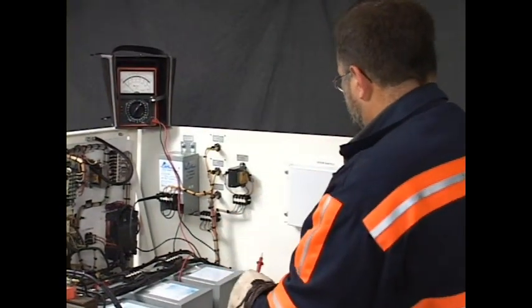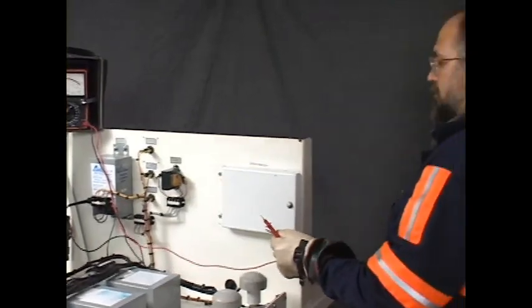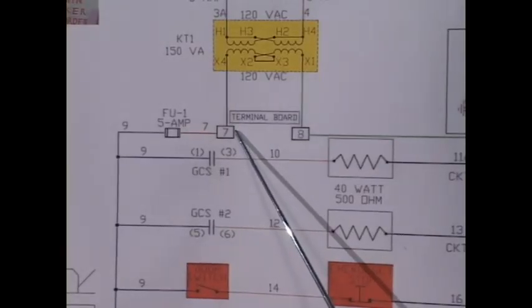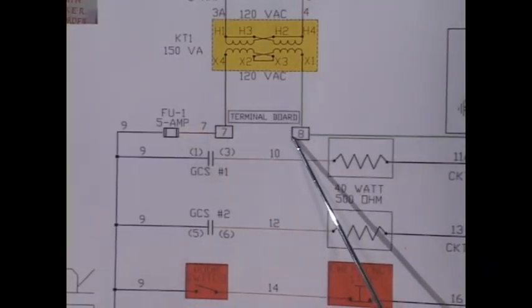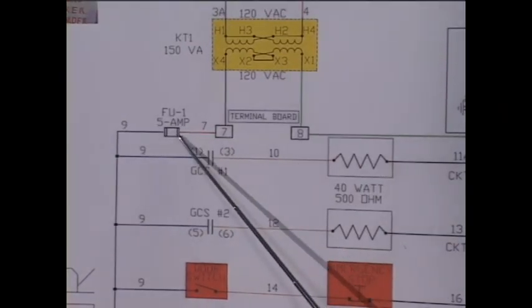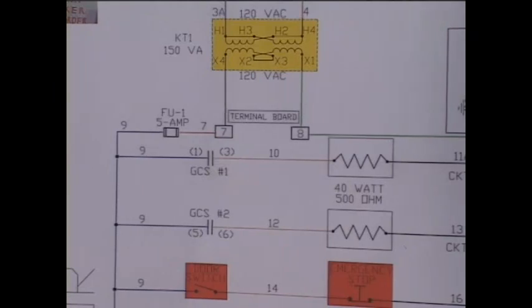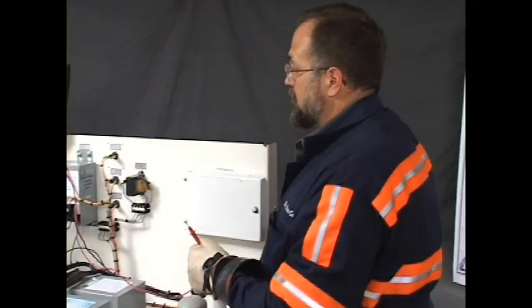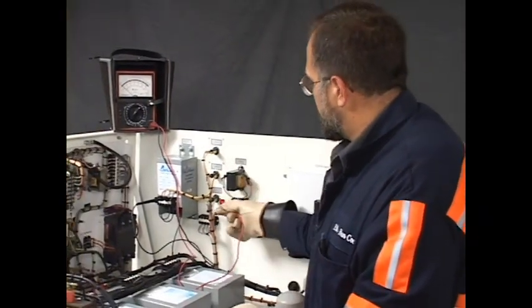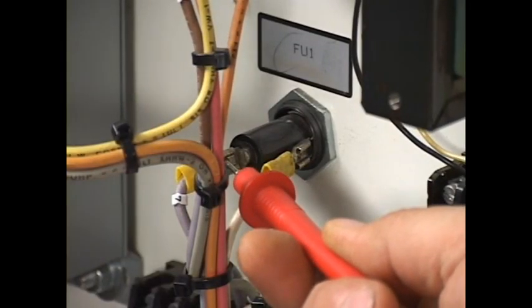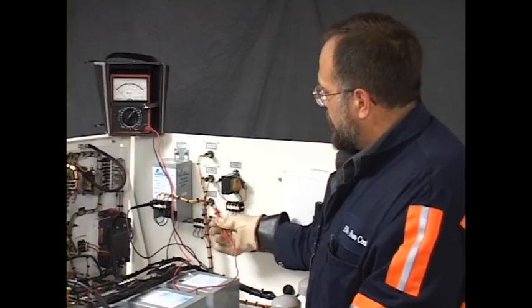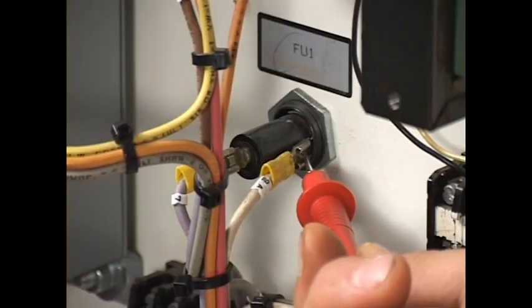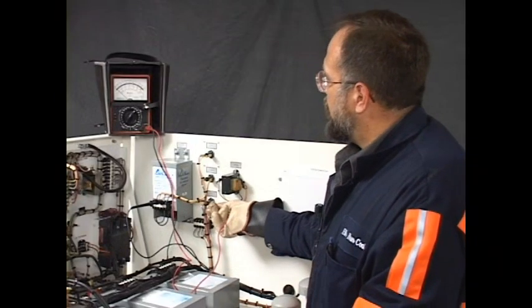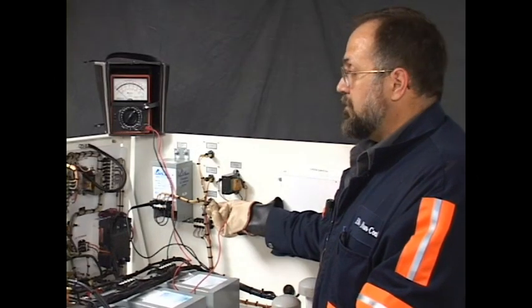Now, with that 120 volts from 7 to 8, I'm going to read from terminal 7 to the fuse. If this wire is open, I'll read 120. If it's closed, I'll read 0. And I read 0. I'm going to read through the fuse to wire 9. It reads 0.